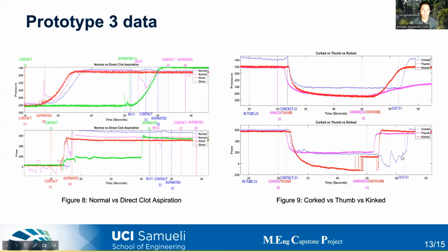In prototype 3, we can see that at 50 Hertz, we collect a lot more data points, and you can see a lot more prominent changes. So here we have normal versus direct clots. We did this comparison due to physicians being able to obtain clots in very different ways. One is when they turn on the vacuum right when they meet the clot, and the other is they make their way to the clot with the vacuum already on. As you can tell, both direct clots begin aspirating the clot around 18 or 20 seconds. For the two normal ones, they get fully aspirated around 30 to 35 seconds and then go back to normal after that.